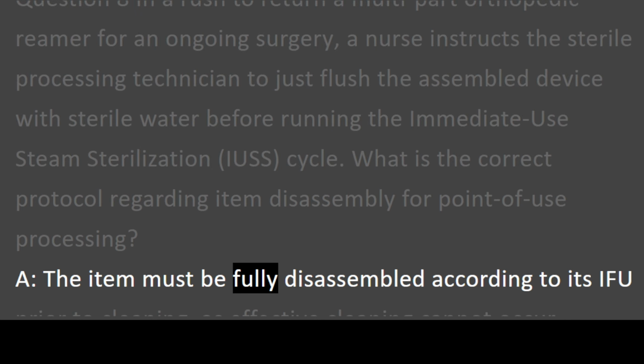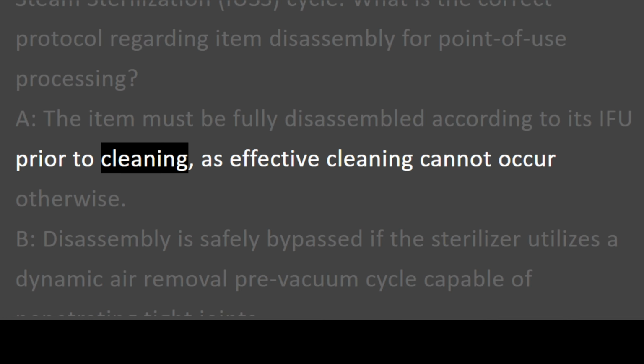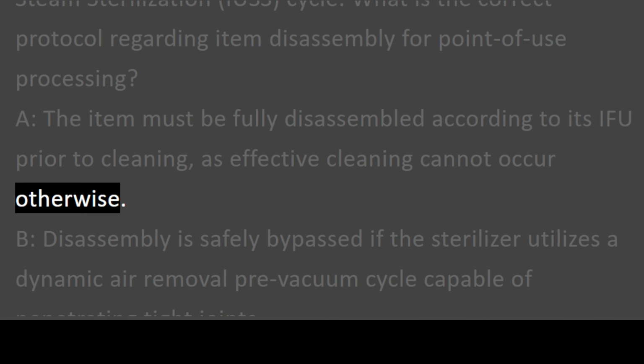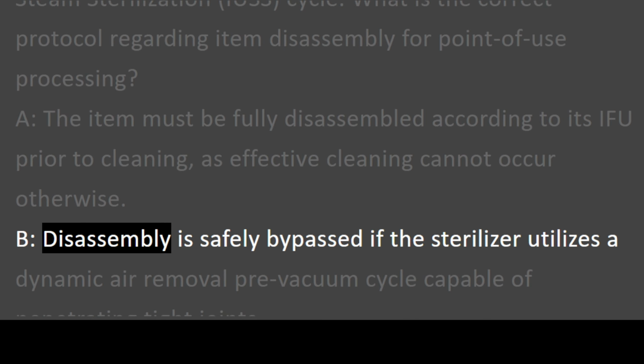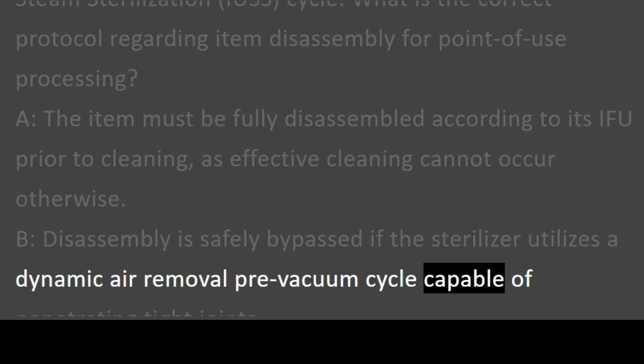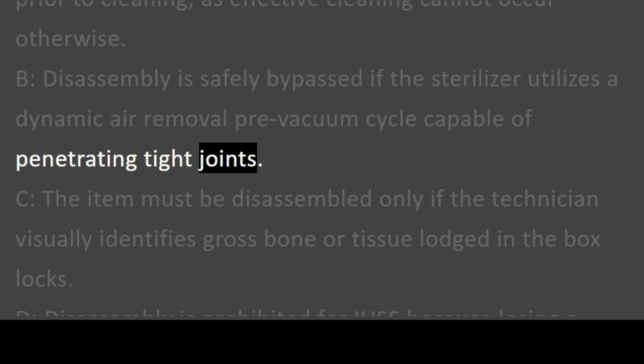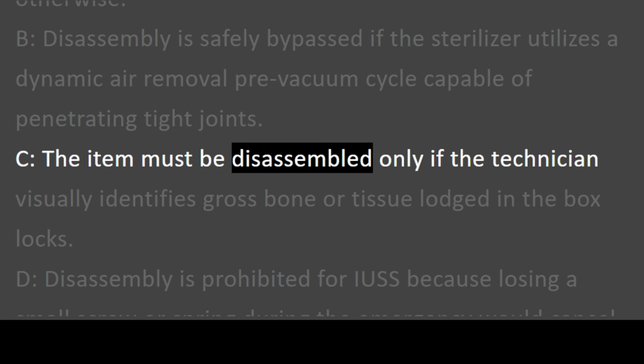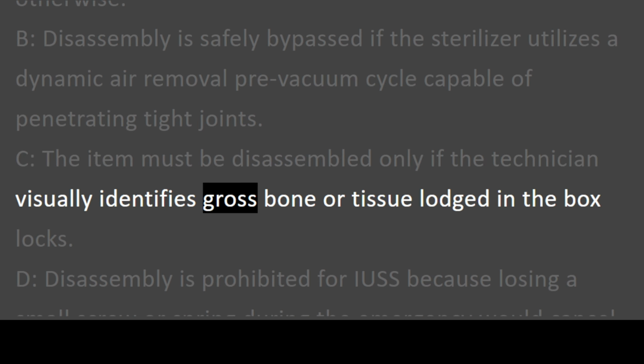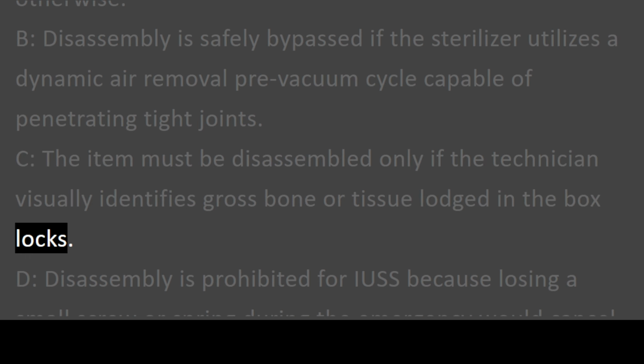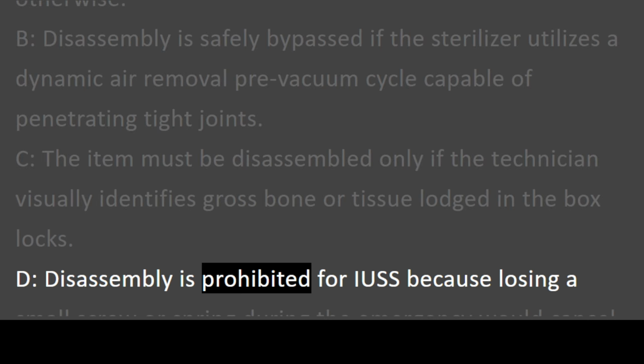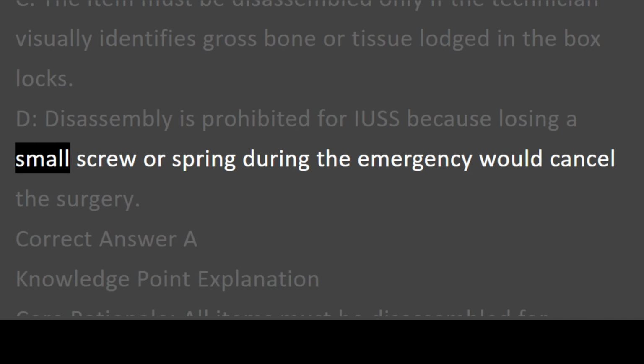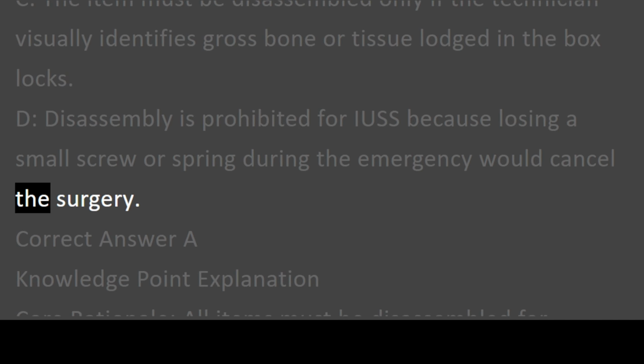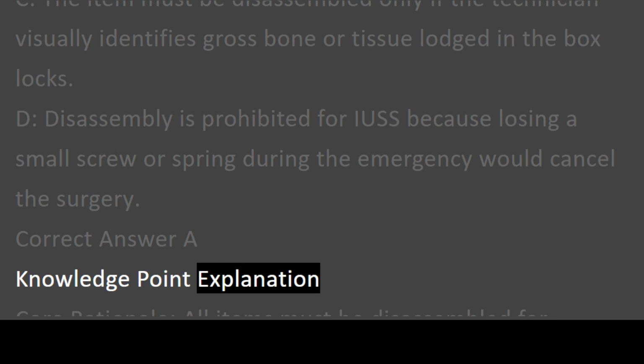A. The item must be fully disassembled according to its IFU prior to cleaning, as effective cleaning cannot occur otherwise. B. Disassembly is safely bypassed if the sterilizer utilizes a dynamic air removal pre-vacuum cycle capable of penetrating tight joints. C. The item must be disassembled only if the technician visually identifies gross bone or tissue lodged in the box locks. D. Disassembly is prohibited for IUSS because losing a small screw or spring during the emergency would cancel the surgery. Correct answer A. Knowledge point explanation.